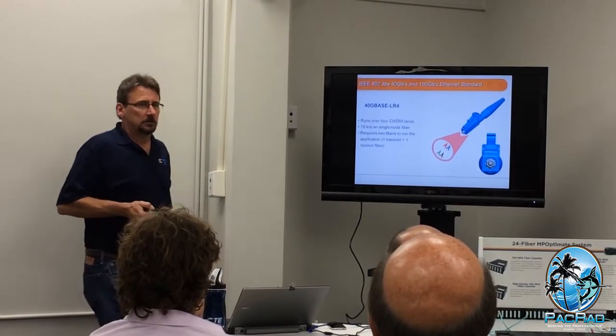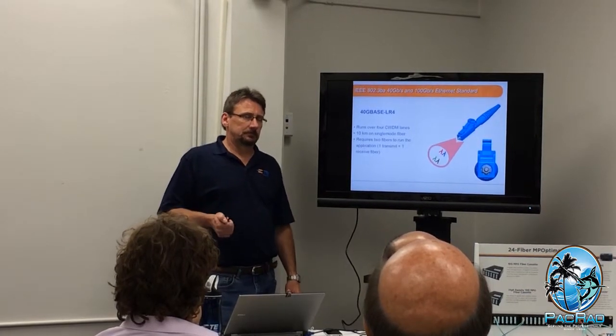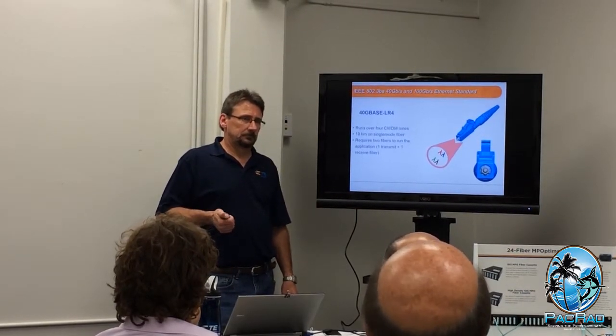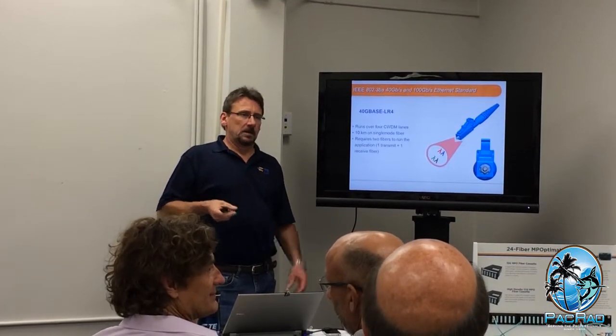What about the 4 dark? What about it? Are they potentially useful in case of a damage? No, because of where they are in the cable. For transmit, you use fibers 1, 2, 3, 4. For receive, you use fibers 9, 10, 11, 12. And because the other ones are just in the middle of the cable, they're not used. In a 12 fiber architecture, they're not used.